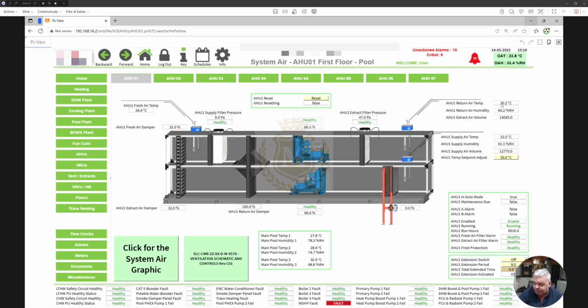Now we can see that we've got 30.2 degrees return air temperature here on this sensor, and we have got 24 degrees on this sensor here coming in. So that way we could do free cooling, because we could bring the air in through there. That's turned off, which it currently is, and it's sending out a temperature of 33.5. Now that is because this is actually recirculating and mixing with the outside air. So we're bringing in the 30.2, we're bringing in the outside air, and it's mixing.